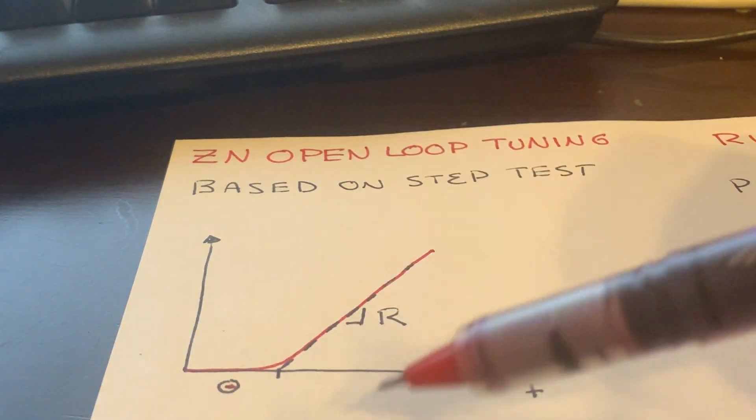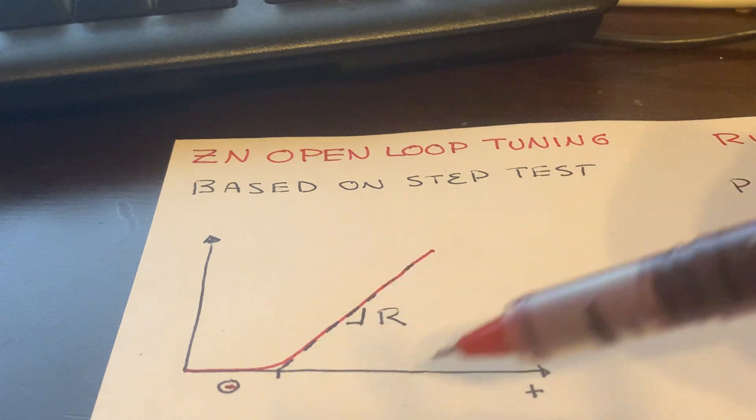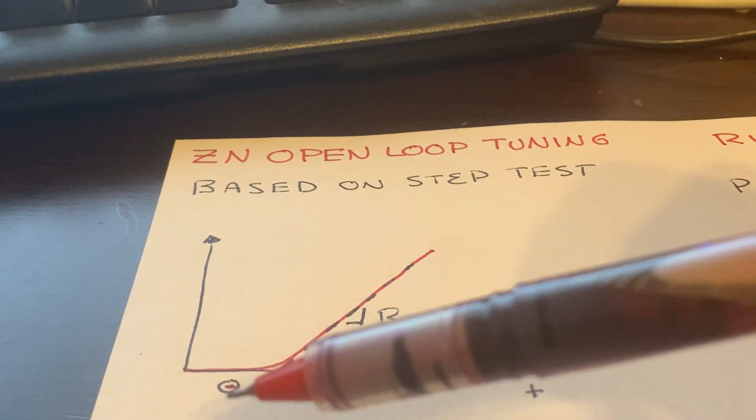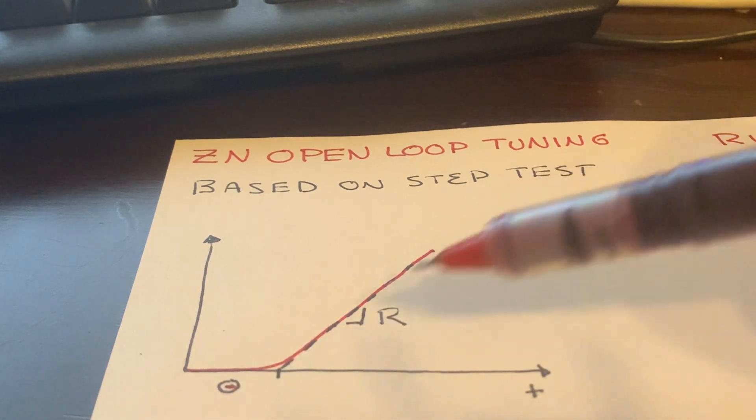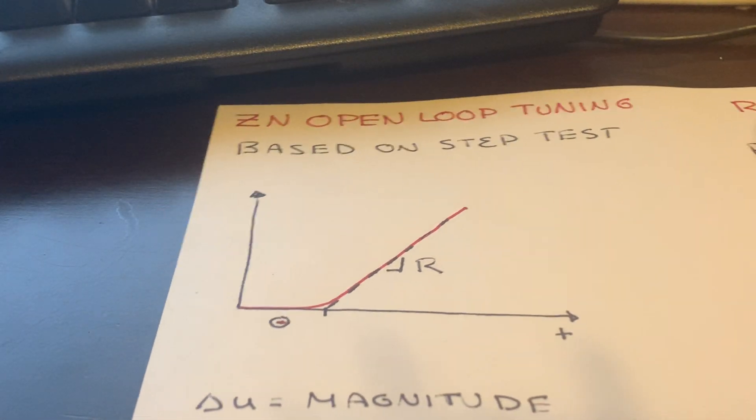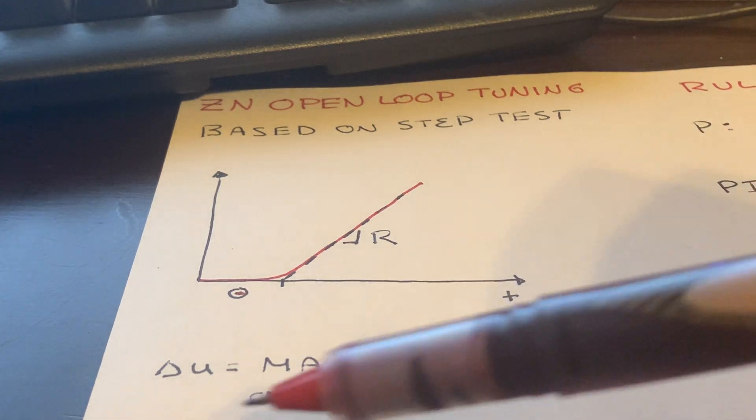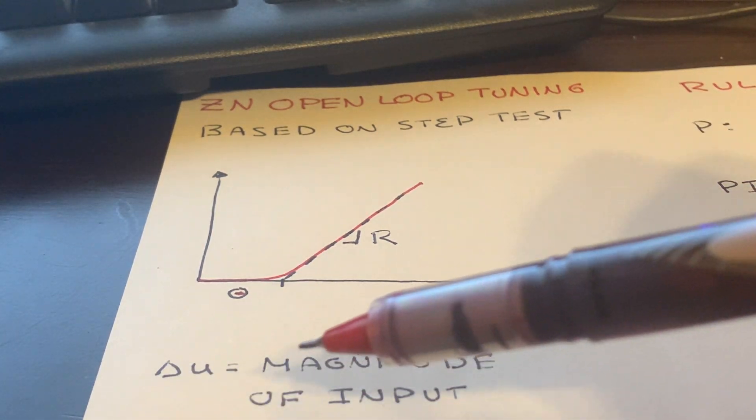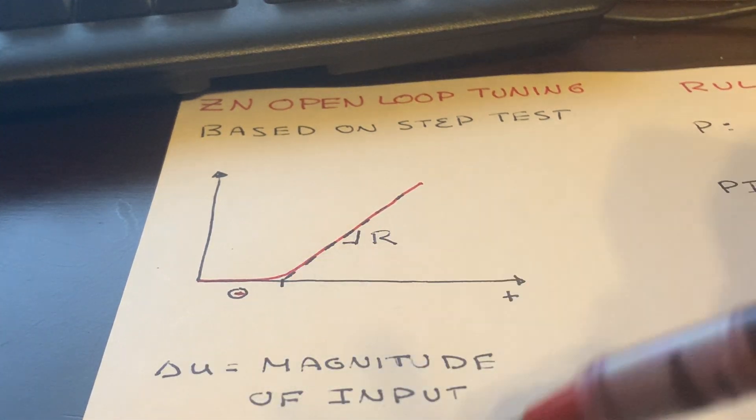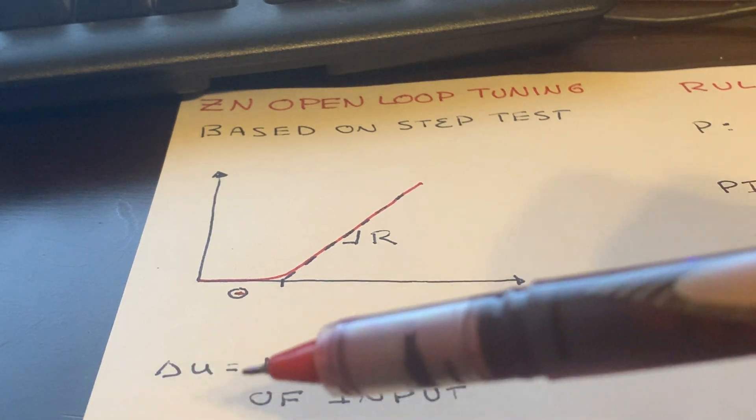But in this open loop tuning, we don't actually care about the steady state value. We just care about the slope r and the time delay theta. These are estimated from process response curves. The other variable we're interested in is delta u, which is the magnitude of the input. For a unit step test, delta u is equal to 1.